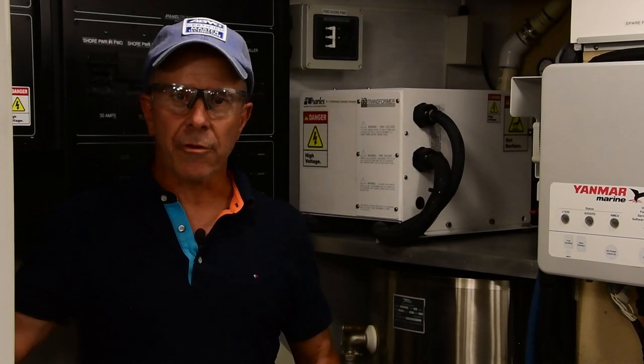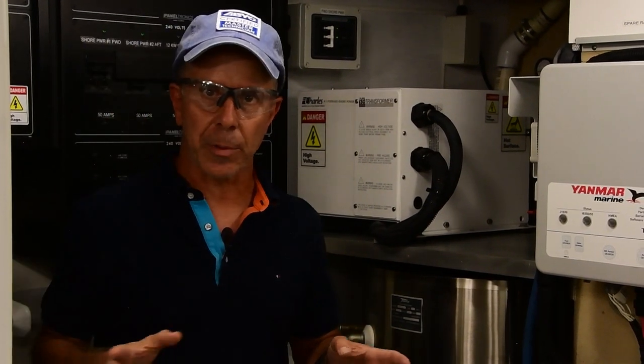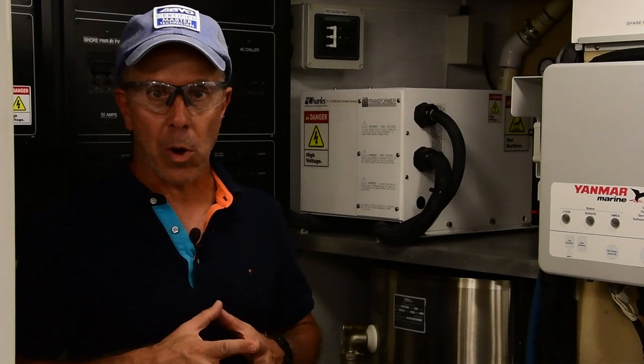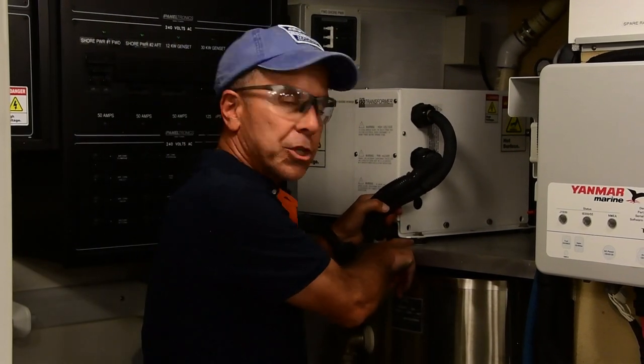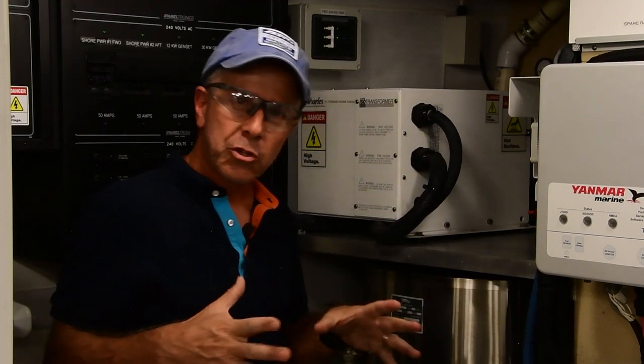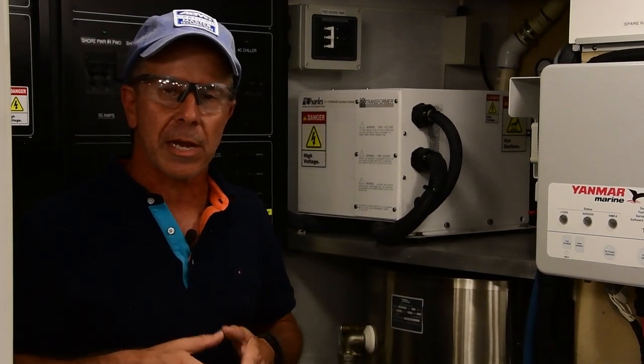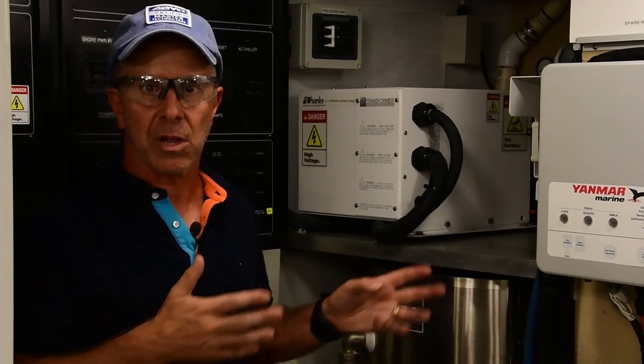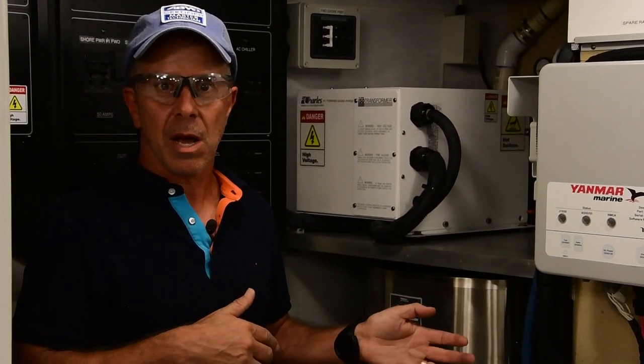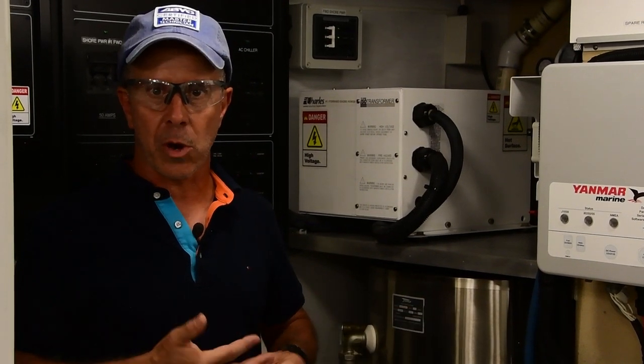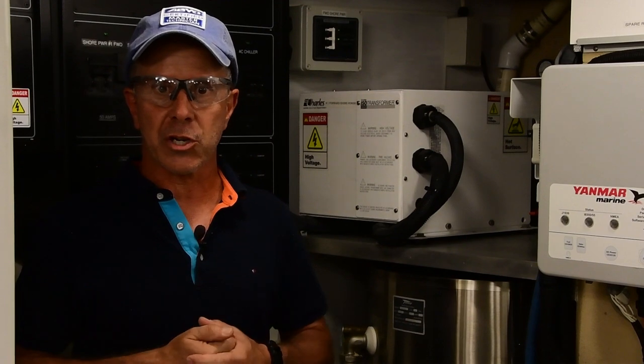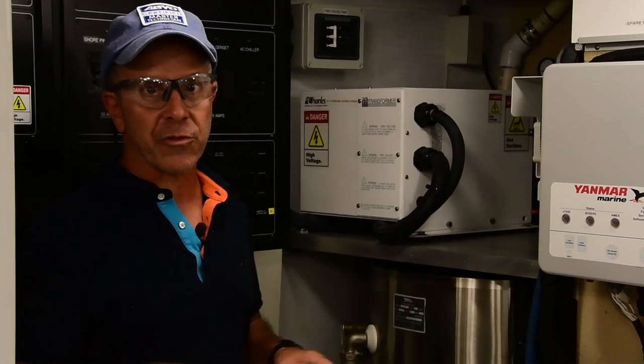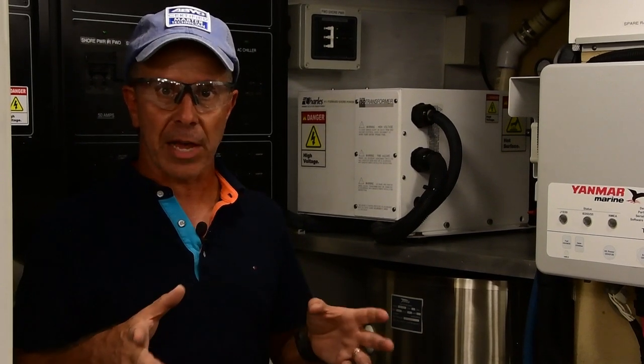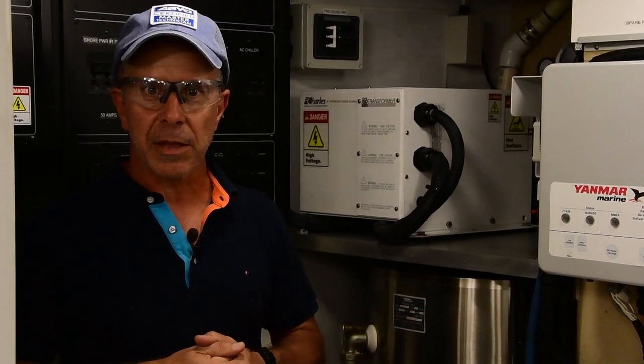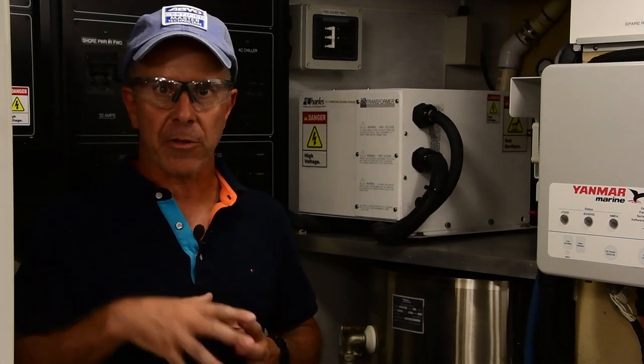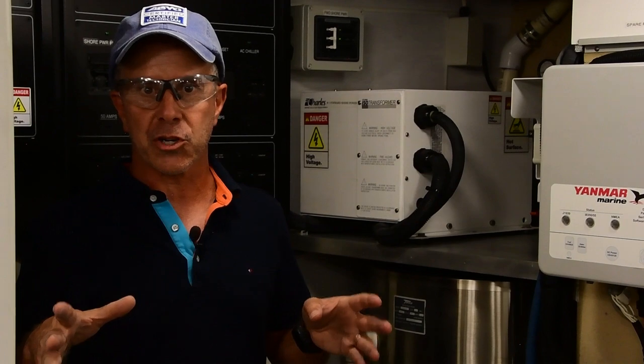All right, another feature of shore power transformers, an optional feature, but an important one, is mounting it on a soft mount, like this bushing that's under this one. Transformers can hum or buzz a little bit when they're working. You don't want to transmit that to the rest of the vessel, especially if the transformer is near or abutting an accommodation space. You don't want to be listening to that noise or feeling that vibration while you're trying to sleep. So shore power transformers should be soft mounted on a flexible mount, sort of a motor mount, if you will, that will absorb that vibration and allow that transformer to float and not transmit that vibration into the boat.